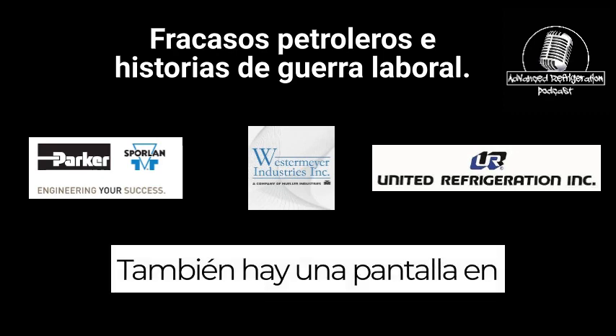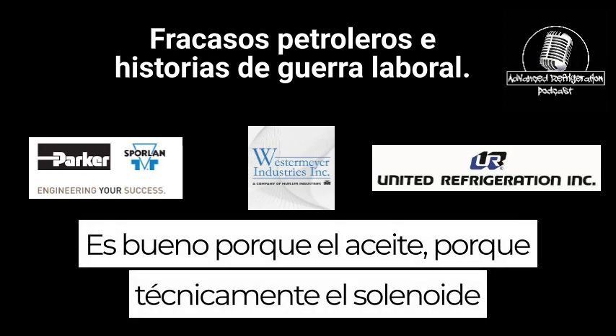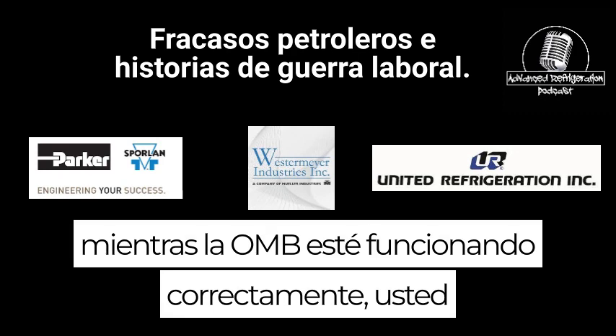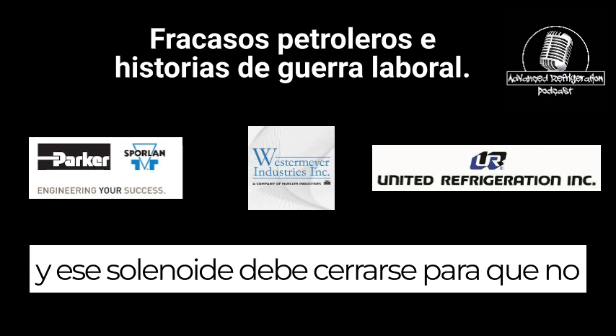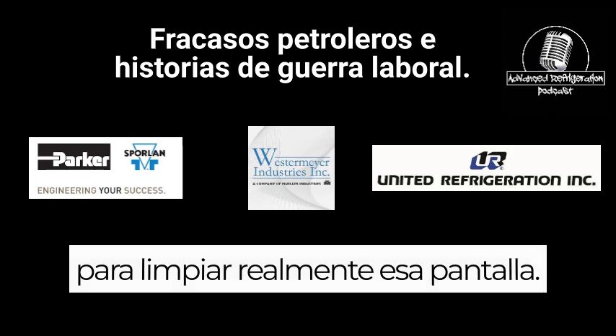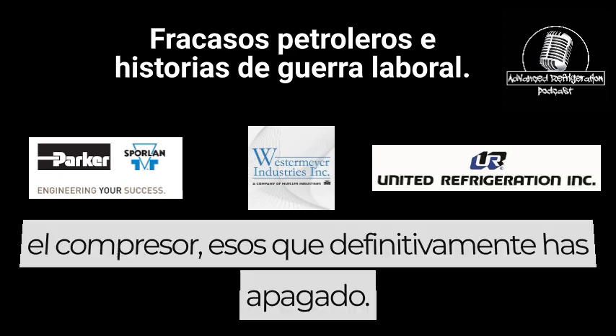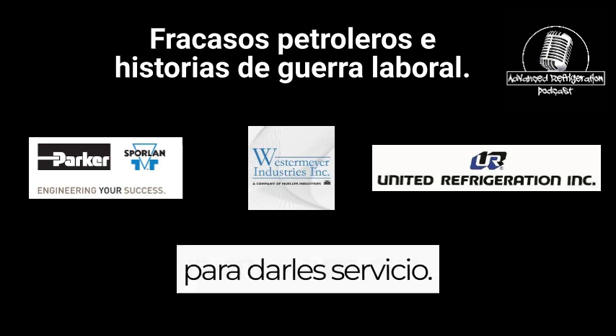There is also a screen in there that is cleanable, is serviceable. It's nice because the solenoid technically should be locked down. As long as the OMB is functioning properly, you would just basically have to close off your oil line in, and that solenoid should shut. So you wouldn't have to technically pump down that compressor in order to clean that screen, unlike your regular conventional mechanical oil pots or oil level controls on the side of the compressor. Those you definitely have to shut down and pump down the whole compressor in order to service them.